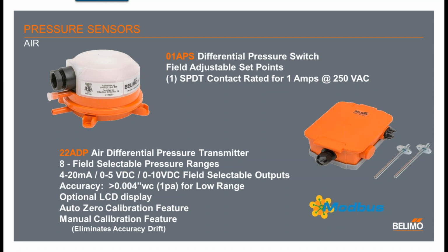You can order the air differential pressure sensors with an optional LCD display. You can order optionally with auto zero calibration feature for the low pressure ranges. And all the devices have manual calibration feature, which eliminates accuracy loss and drift over time. Modbus RTU can also be selected in any of the devices.